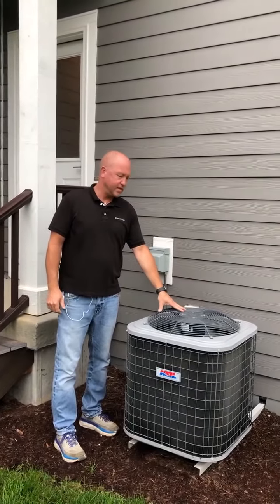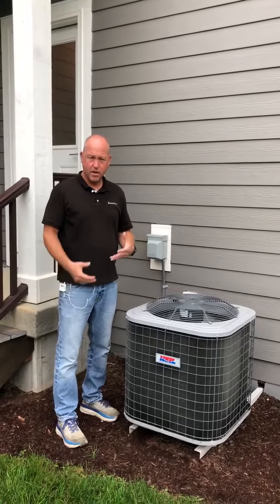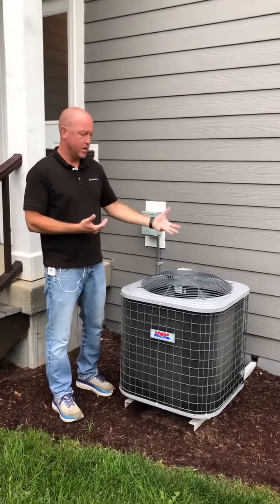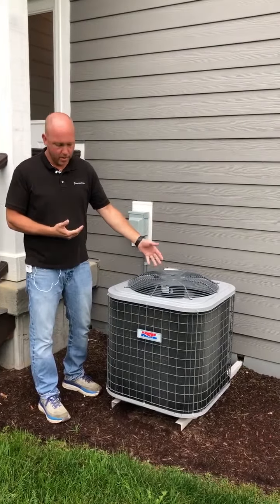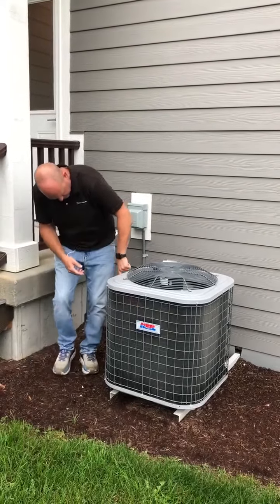Homeowner maintenance on your HVAC system in regards to the air conditioning. If you ever find that your air conditioner doesn't seem like it's performing like it used to, come out here and make sure the unit's running, but also do a visual inspection of the coil here.